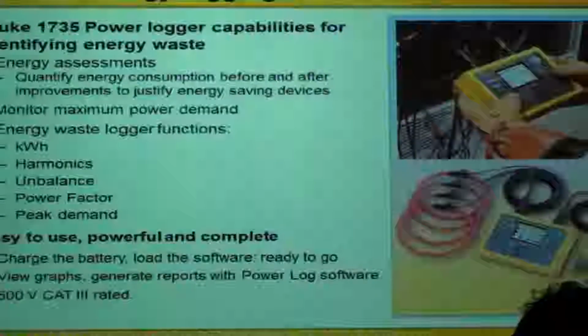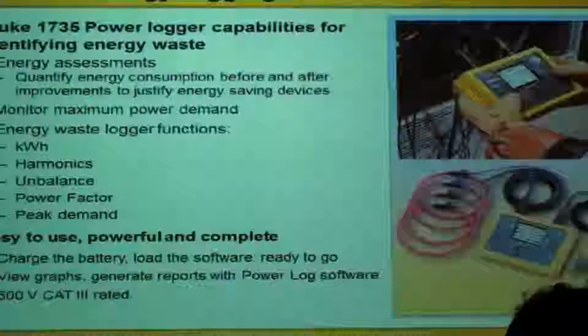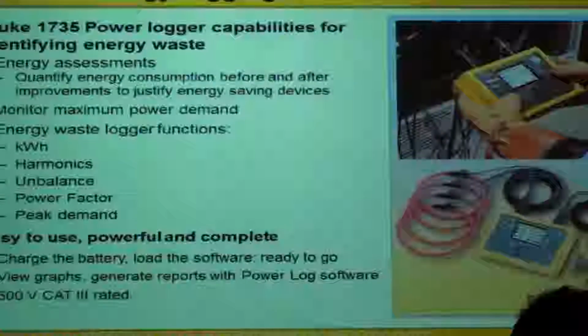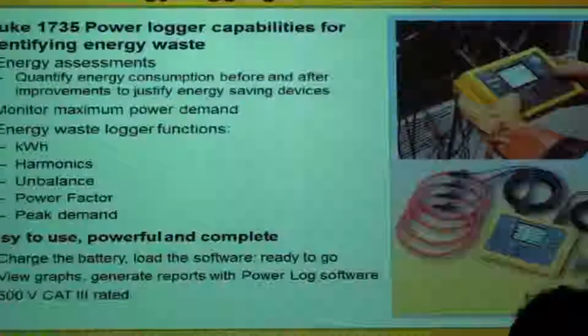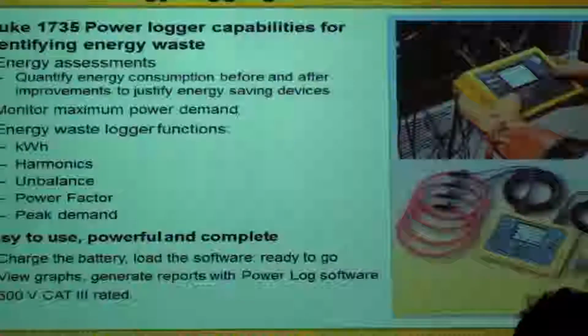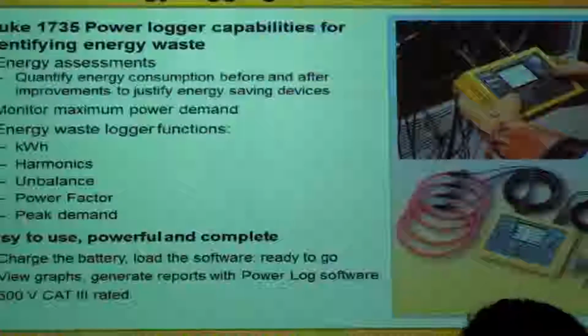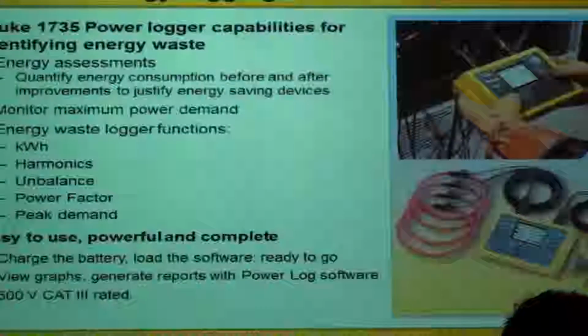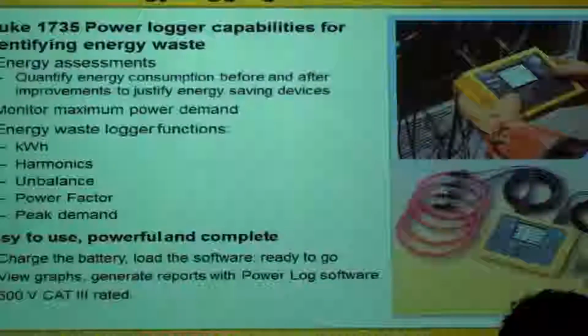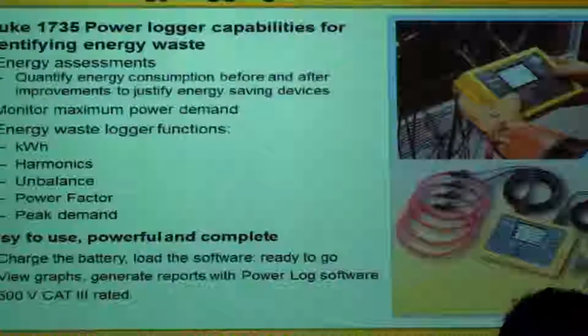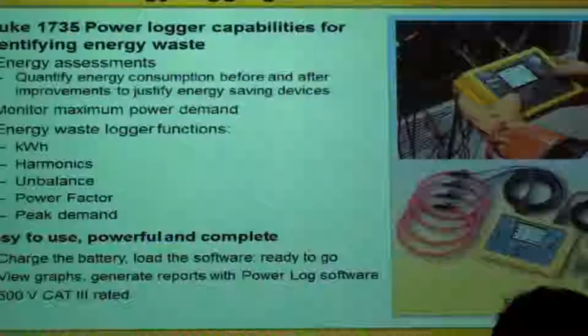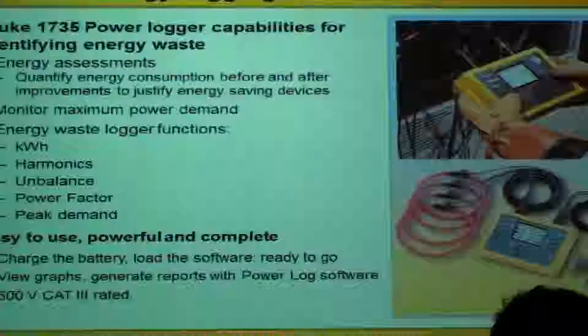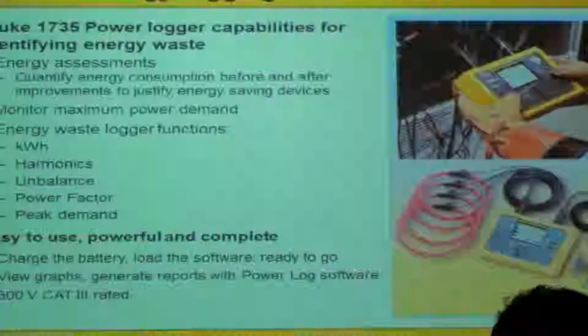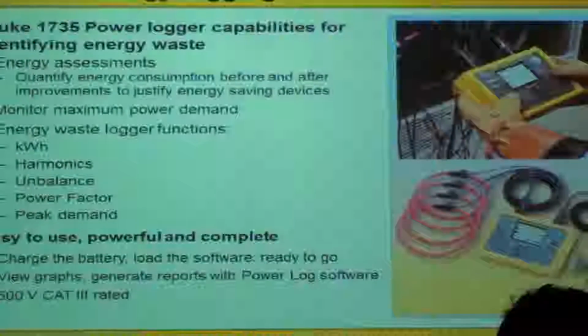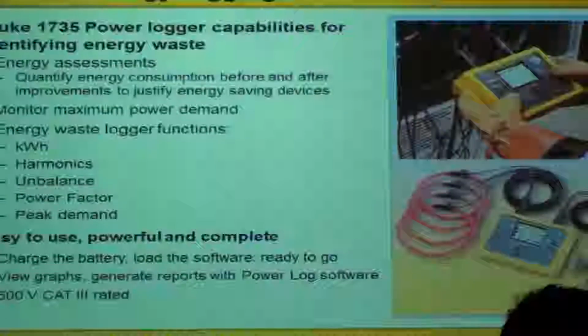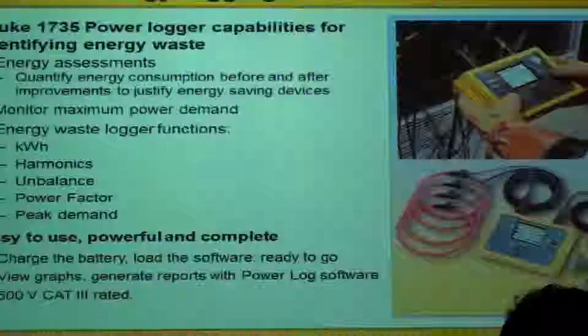Energy logger functions: it will measure and give you the kilowatt hours. It will tell you the harmonics, how much harmonics you have, what is the unbalance in your system, what is the power factor, and what is your peak demand as well. Because what the meter does is you can set a sampling averaging of 15 minutes, and let's say you do a measurement for a month. When you export it to your software, you just put the cursor at the maximum point, and that becomes your peak demand. That's the maximum demand I've had.